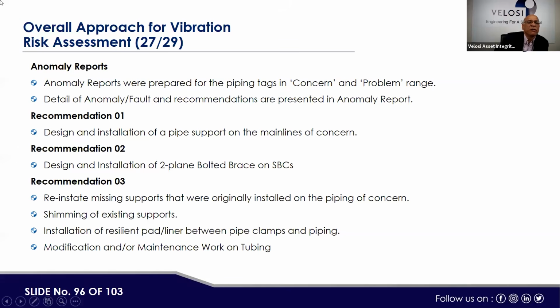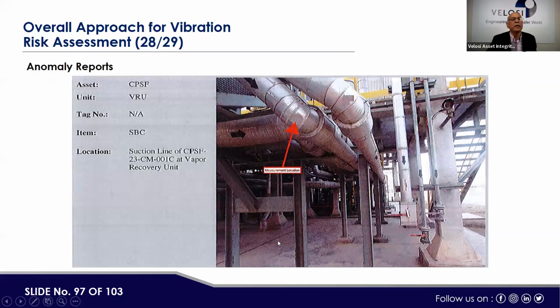Recommendation 1 given: design and install piping support on the main line of concern. Number 2, design and installation of 2-plane bolted braces on SBCs. Recommendation 3, reinstate missing supports that were originally installed on the piping of concern. Shimming of existing supports, installation of resilient pad liner between pipe clamps and piping, modification or maintenance work on tubing. Here, one of the recommendations is for the suction line of CPSF number 3 at the vapor recovery unit, where some correction to the support was recommended.